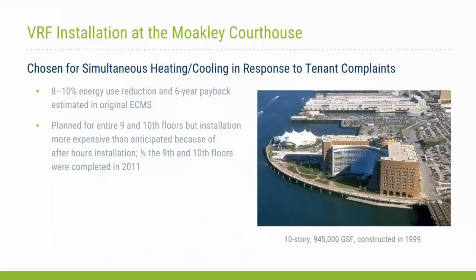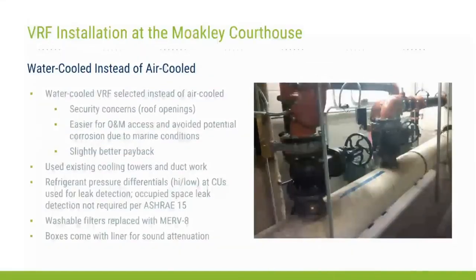Next slide, please. We did end up using a water-cooled instead of air-cooled system there at the Moakley. The reason we selected that was there are a few security concerns from the marshals and the courts, mostly the roof openings that we would have had. It was a little bit easier for our O&M to access the equipment and avoid potential corrosion due to marine conditions. If you saw the photo there, the Moakley Courthouse is on a pier out into Boston Harbor. And then when we looked at the finances and the payback, it had a slightly better payback to do that. So we ended up using existing cooling towers and an existing heating plant to give both heat rejection and to give the system heat.